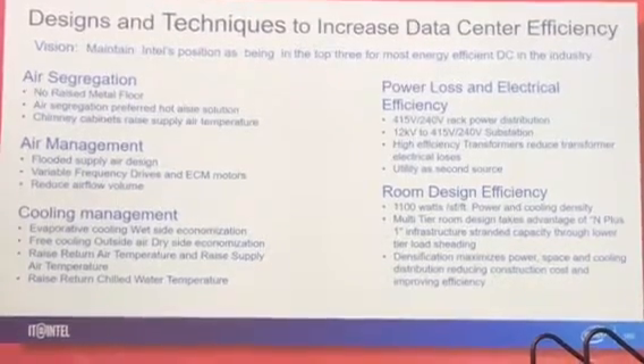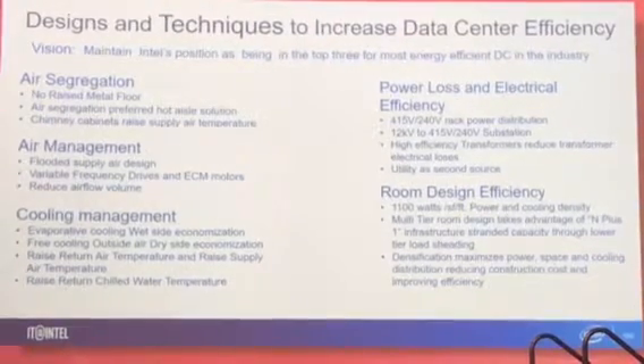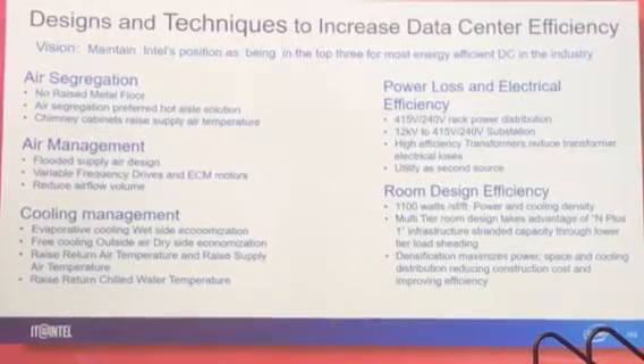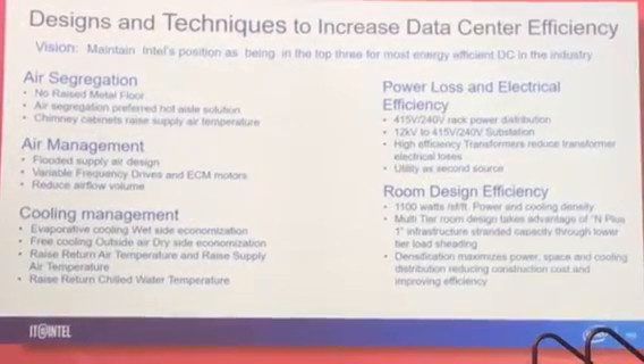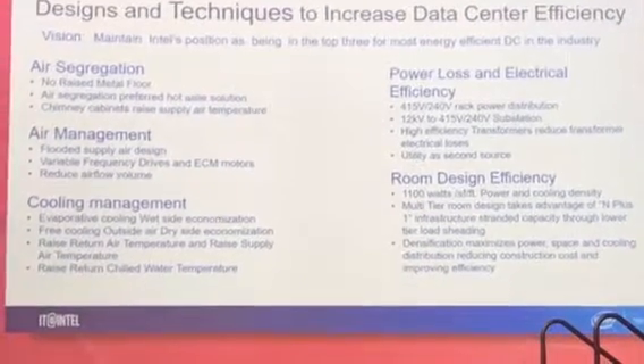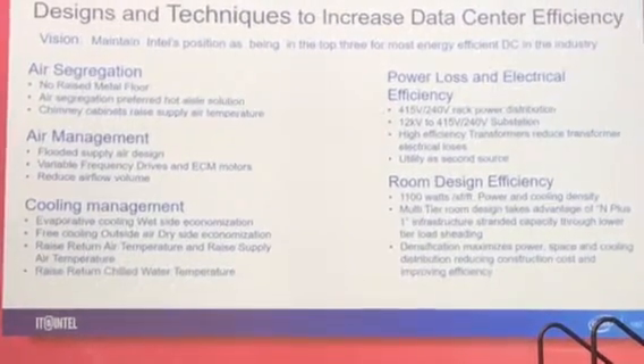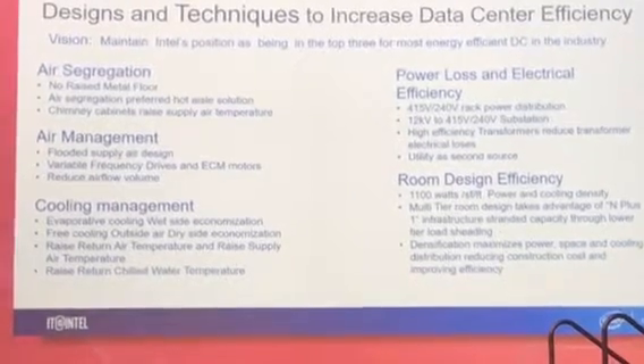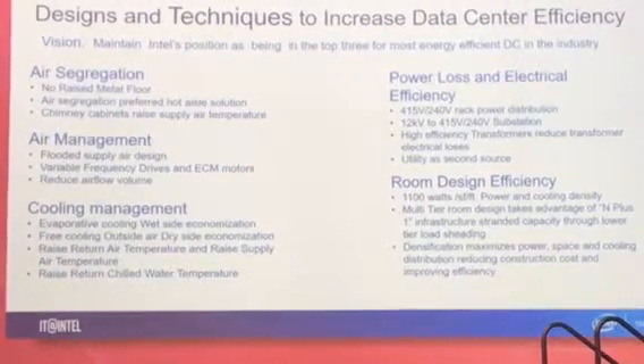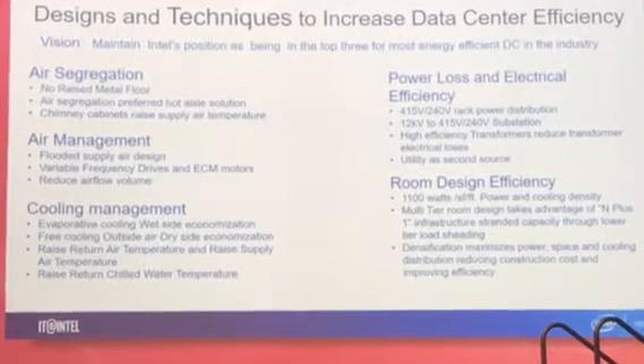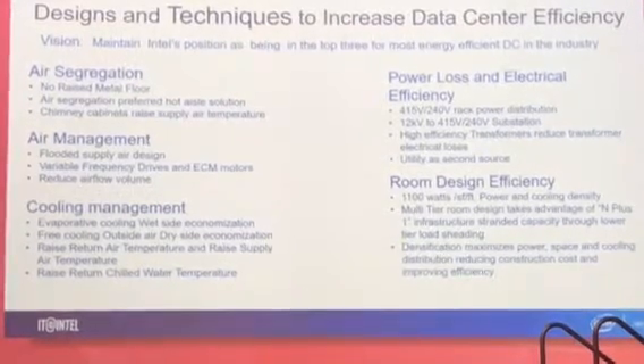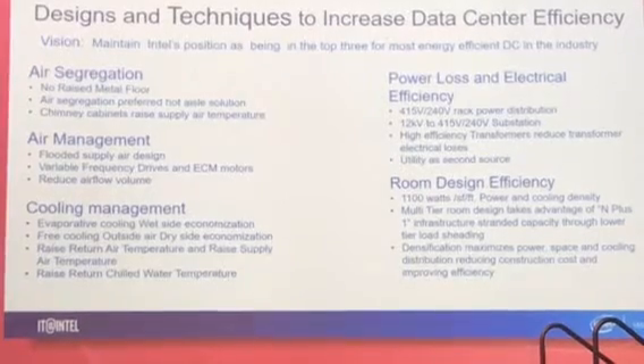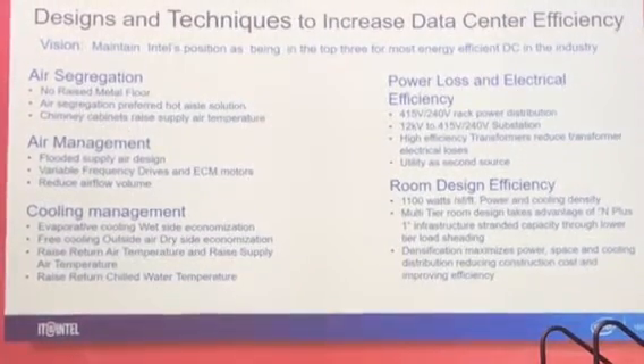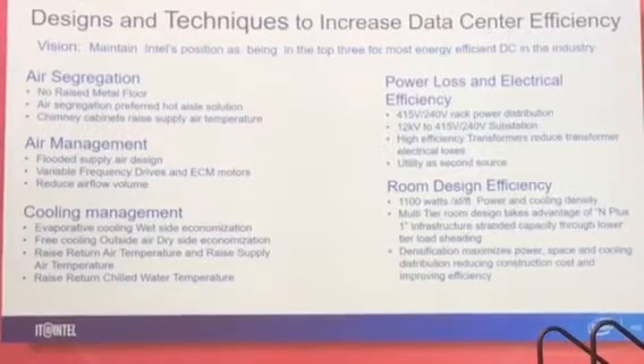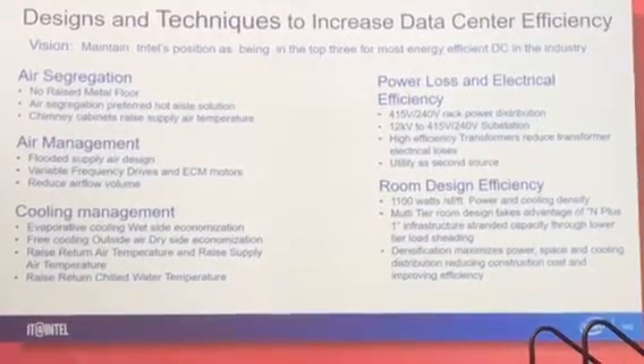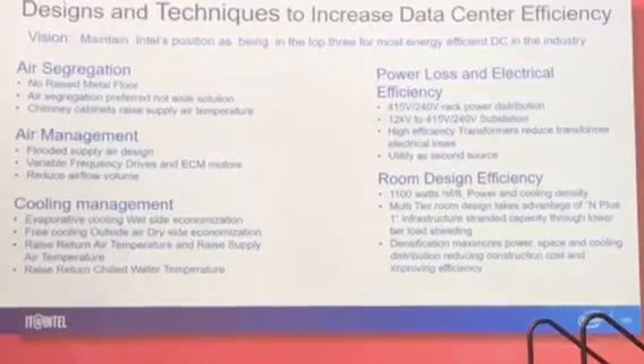High efficiency transformers, and in some cases, not in those 2 data centers, where we need A and B feeder, UPS, and another feeder, we use the other as utility because the UPS is really reliable. So if something happened to utility, the UPS keeps the server running. We also use, like I said, 1,100 watt per square foot, a multi-tier room design instead of splitting between many data centers, and this densification maximizes power and space and cooling.